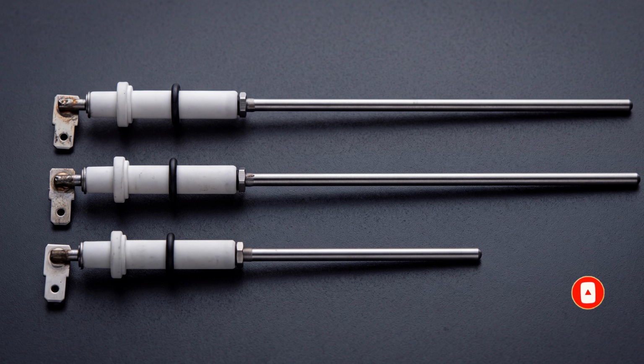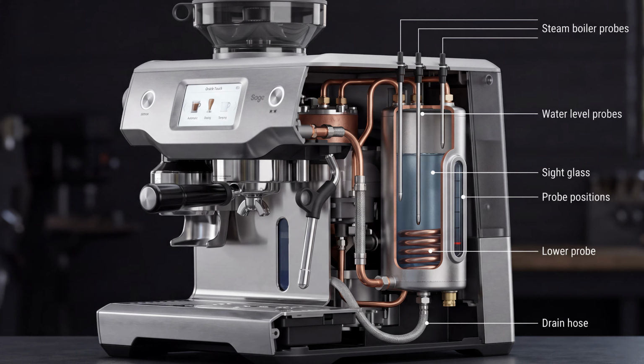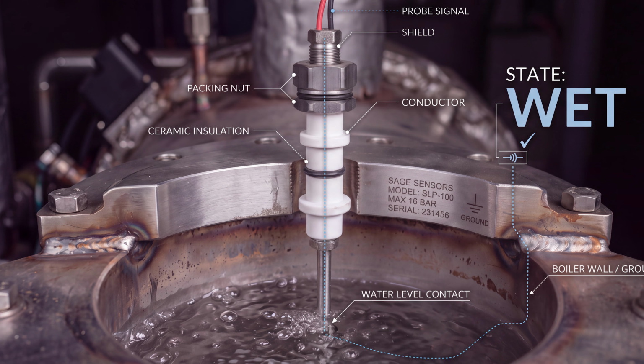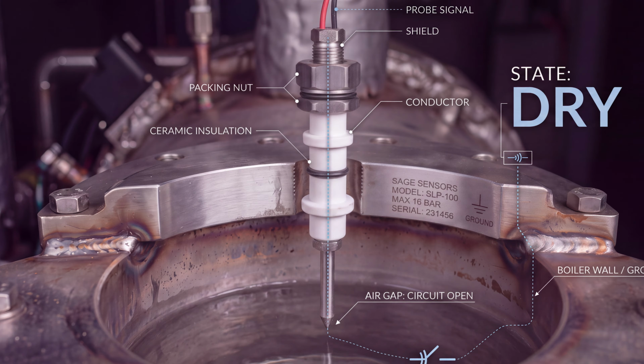It can't see the water. It doesn't use a mechanical float. Instead, it relies on these water level probes. The principle is actually very simple. A metal probe extends down into the boiler and is electrically isolated from the metal boiler body. When water touches the probe, the water creates an electrical path between the probe and the boiler. The electronics read wet. When the water level drops below the probe, that electrical path should disappear. The electronics read dry. That's basically it.